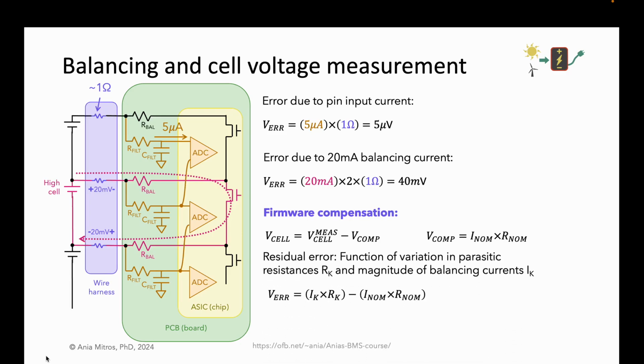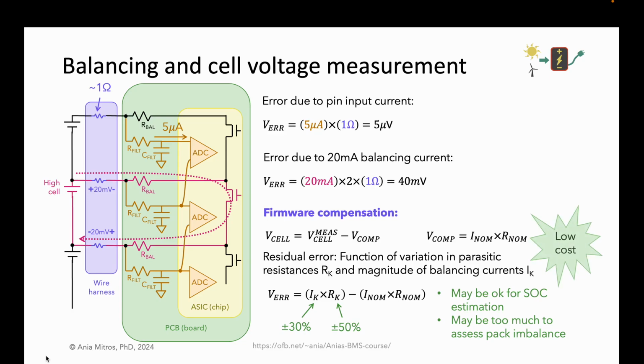The residual error will be a function of the variation in wire harness impedances and the magnitude of balancing currents. You can and should characterize this variation for a specific design, but I might guess that balance currents may vary by 30% due to temperature and component variation and aging, and parasitic resistances may vary by 50% or even more. The resulting residual error may be fine for some SOC estimation purposes, and yet, in many cases, may be too much for assessing pack imbalance. Firmware compensation is a good idea to consider and relatively low cost to implement.